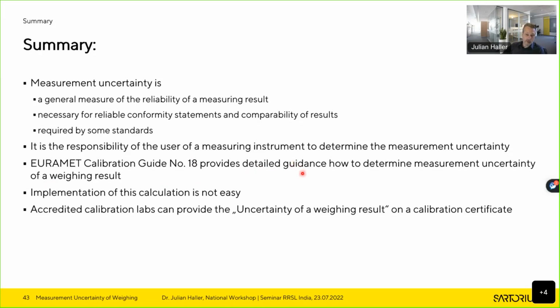And that's why I personally would also always recommend to let some experts do that for you. And usually accredited calibration labs will provide this uncertainty of a weighing result on calibration certificates. And then, of course, it is much easier for the user than doing all these calculations on his own. And as you've seen, once you have that straight line formula for the uncertainty of a weighing result from a calibration certificate, it is quite easy to either calculate the uncertainty with Excel or even let the weighing instrument do the calculation for you.